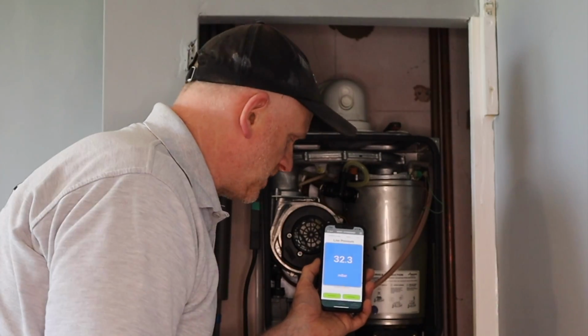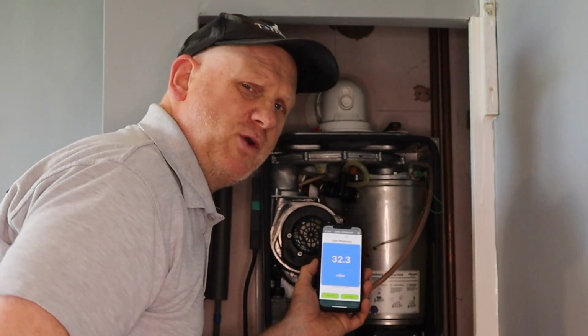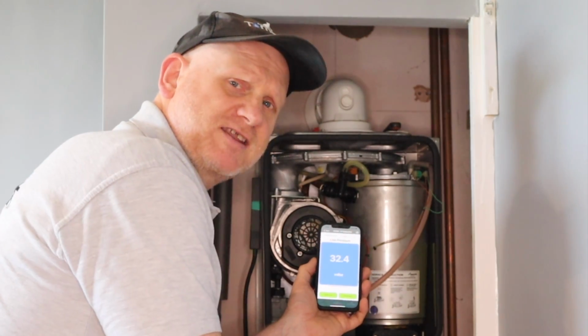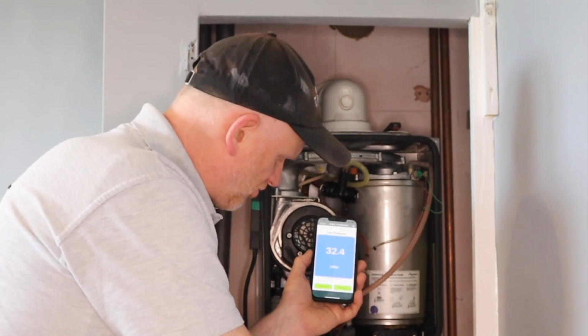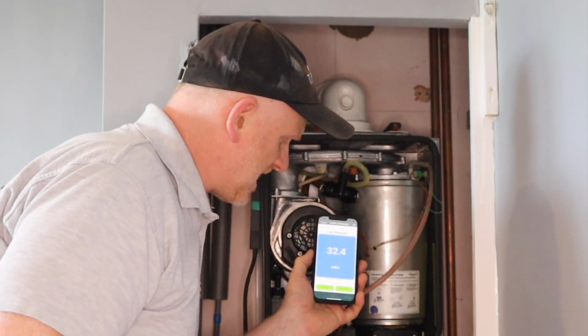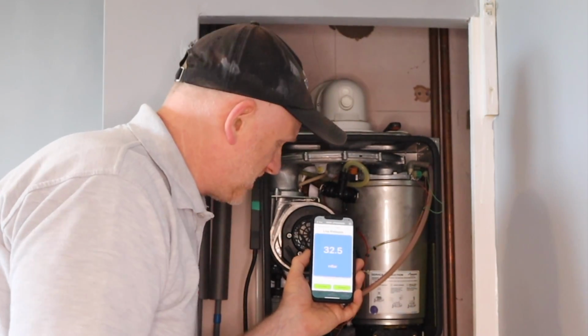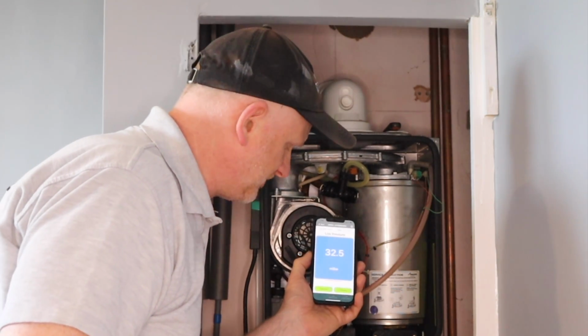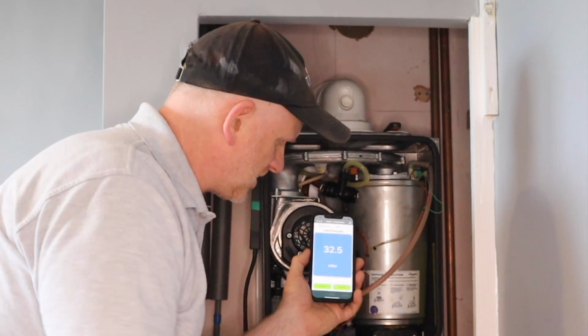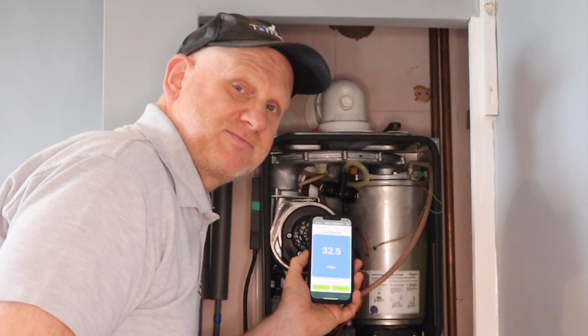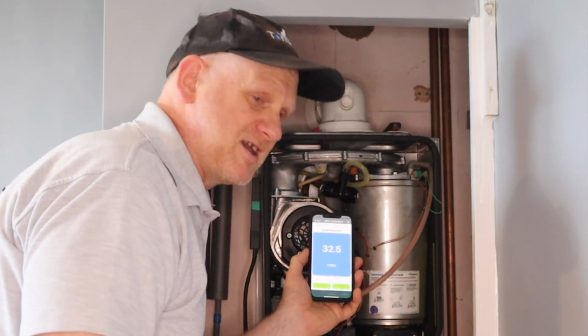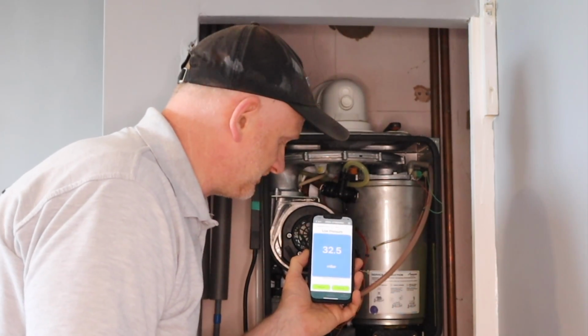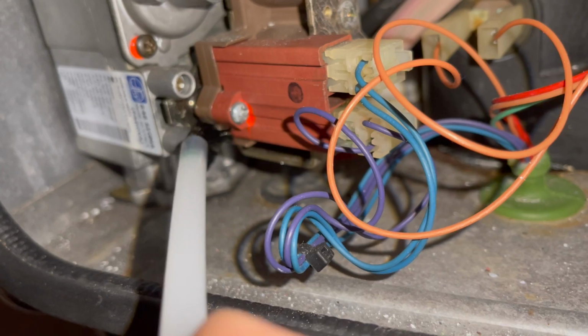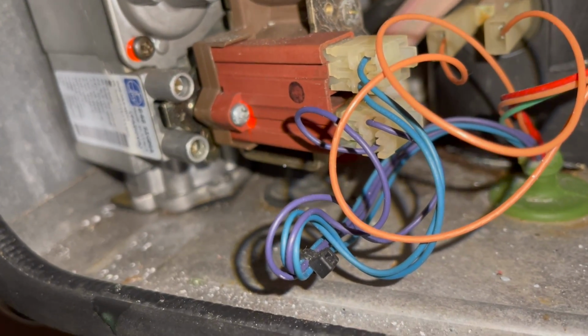So we've got 32.3. Now, there's not a lot we can do about this on this LPG. This is the only appliance on this LPG system, and the second stage regulator is just on the other side of that wall. So the 22mm pipe comes straight up and in, and it's still dropping down to 32.4. But there's nothing we can do about this. There's no adjustments we can do on the inlet pressure, because we can't adjust the regulators. So we've gone down to 32.6 on the inlet pressures. Like I say, there's just not a lot we can do about it. Always remember, once you've done a test nipple, bit of leak detection fluid on there to make sure it's not leaking.